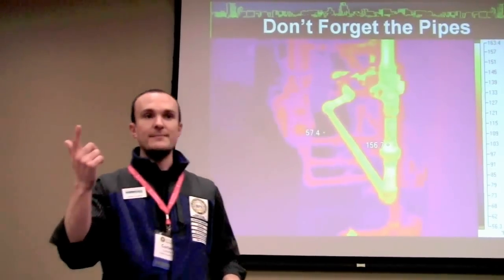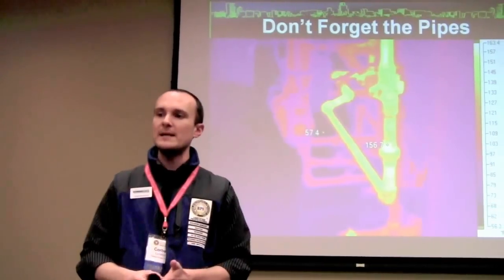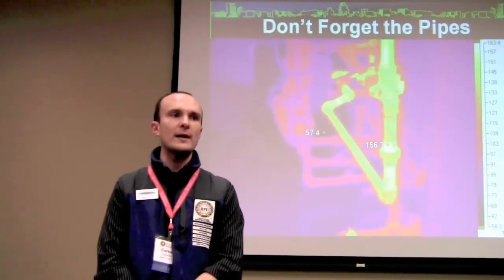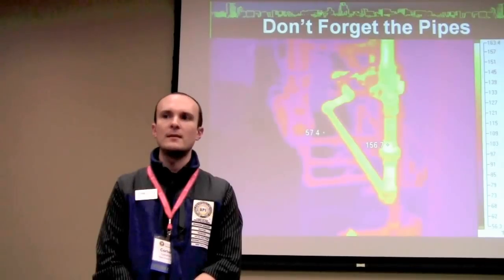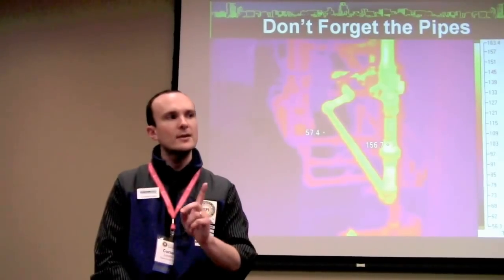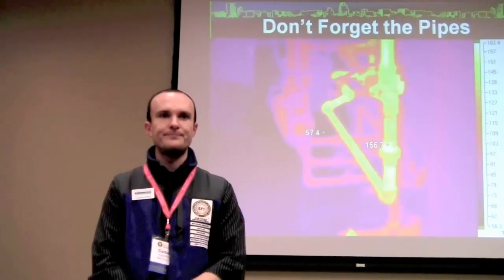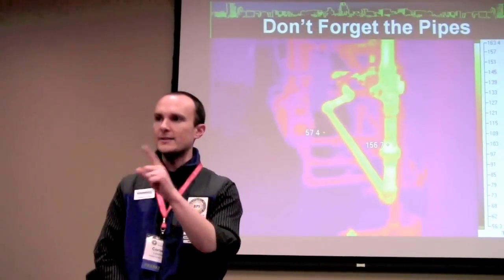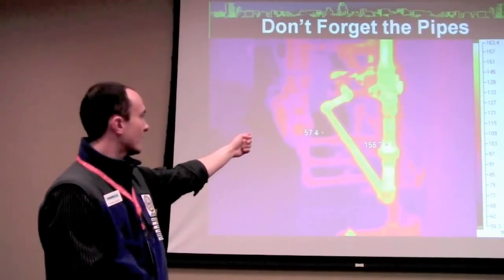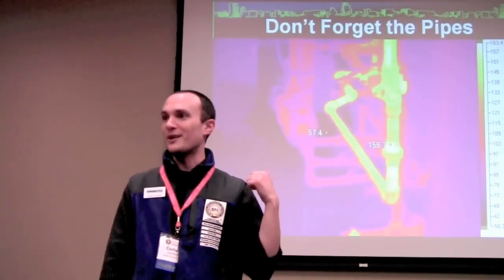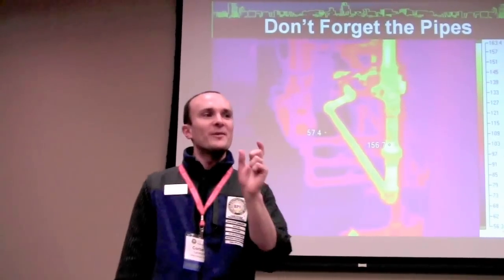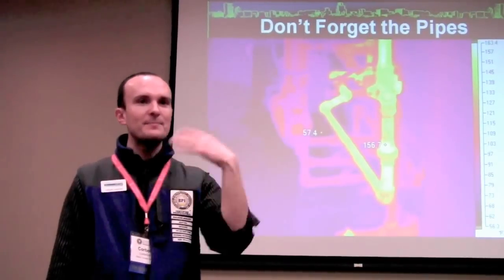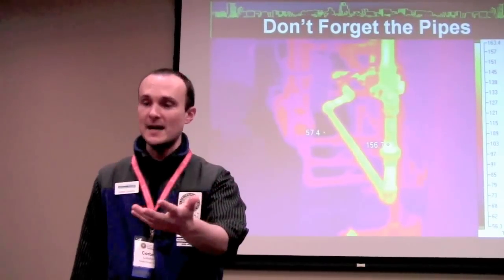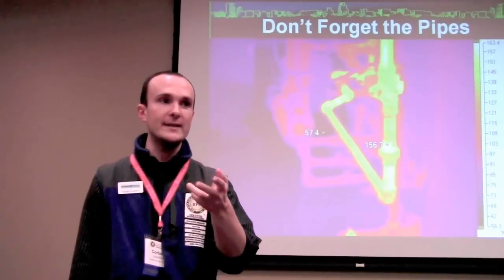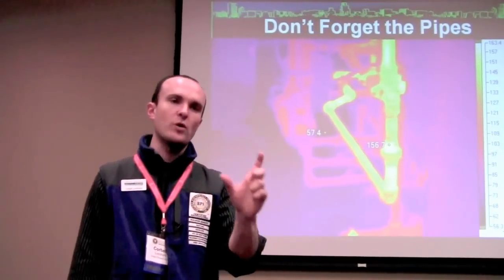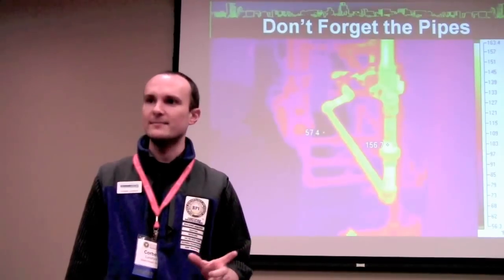Now, pipes — do we insulate pipes in conditioned space? Does anybody do that right now? Anybody in the room? Okay, here's my argument for why you should. Heat flow, right — hot to cold. Inside these pipes it's 160 degrees because this homeowner has it turned way up. So the heat flow from the pipes to the space — we're talking about a domestic hot water system here, the drinking water, the shower water, all that stuff. What is that system for? What is the function of your water heater?